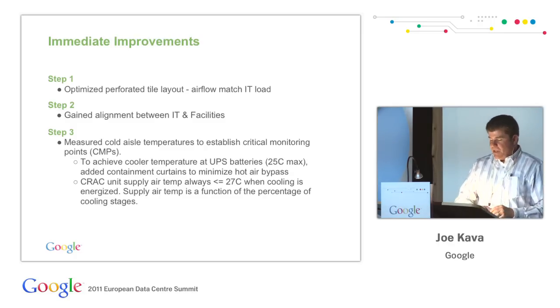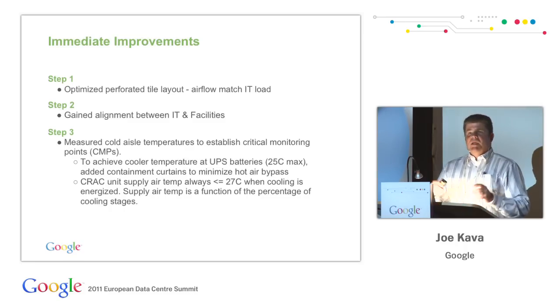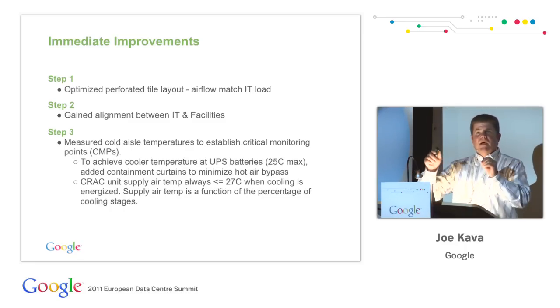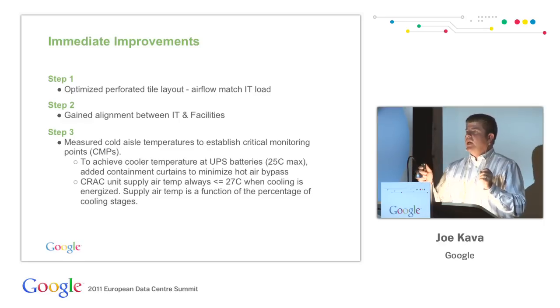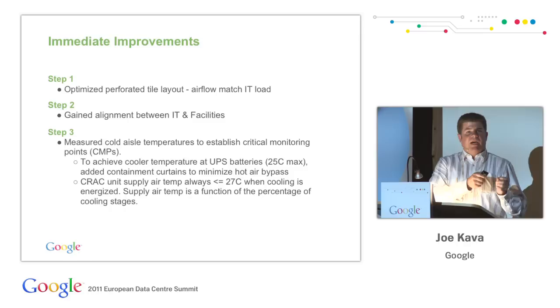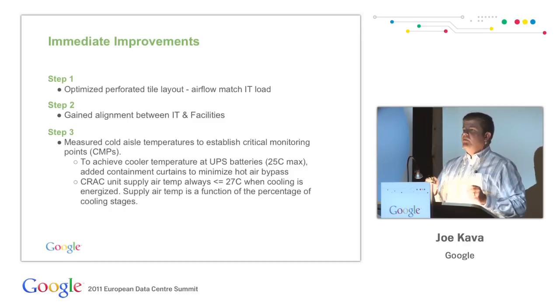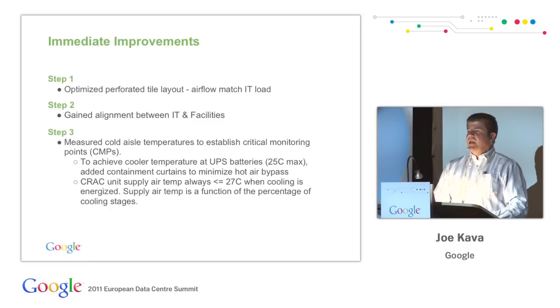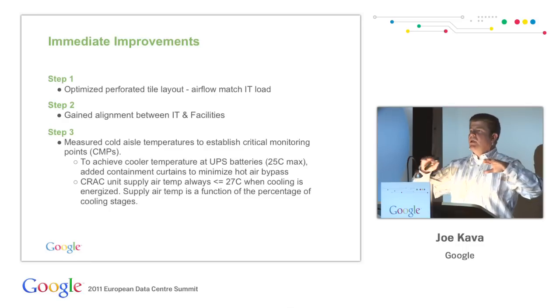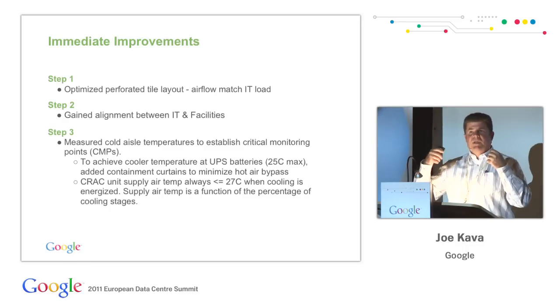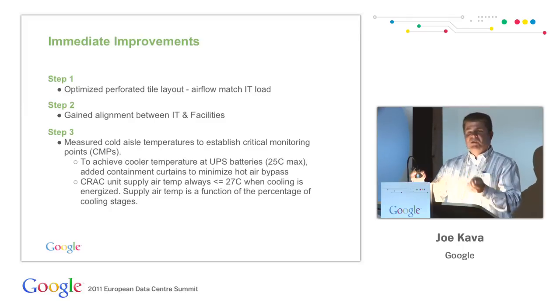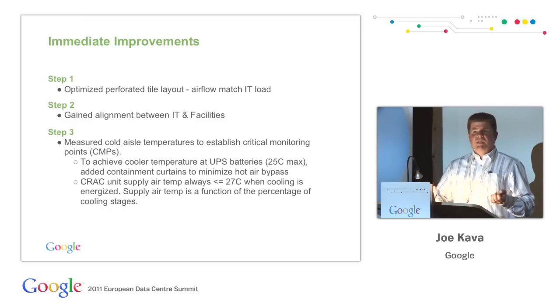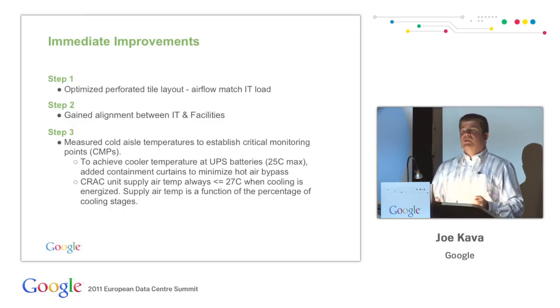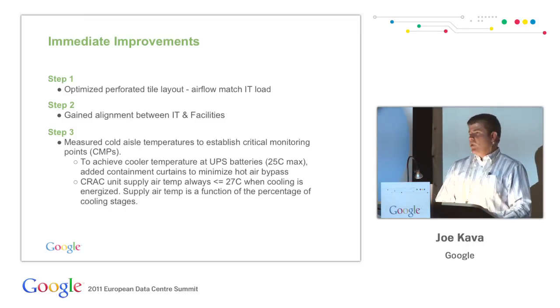The next thing is that we established critical monitoring points so that we could really understand what the temperature distribution was like in the cold aisle. So we set up monitoring points in front of the higher density cabinets, in front of the lower density cabinets, and most importantly, in front of the UPS battery cabinets, so that we had a good understanding of the temperature distribution. The measurements are always the first step, knowing what you have. So we use that as our baseline so that we could track our improvements and make sure that we weren't exceeding any temperature requirements that were going to jeopardize the equipment.